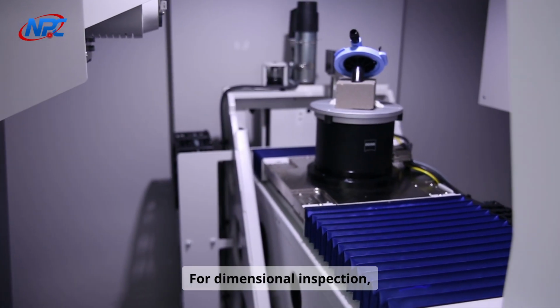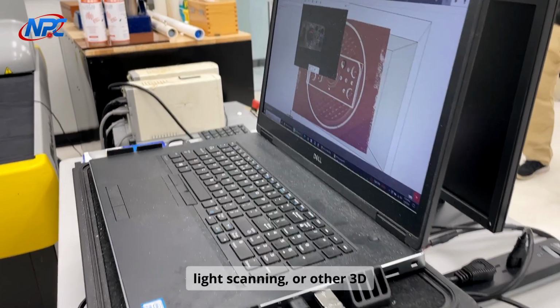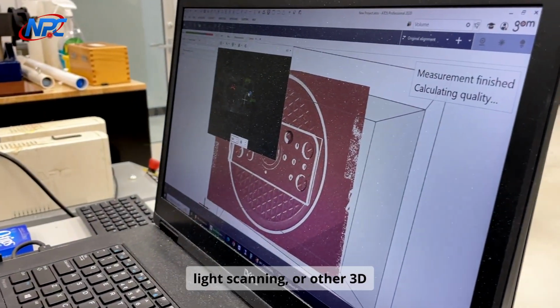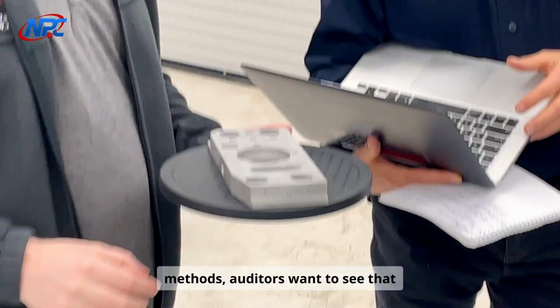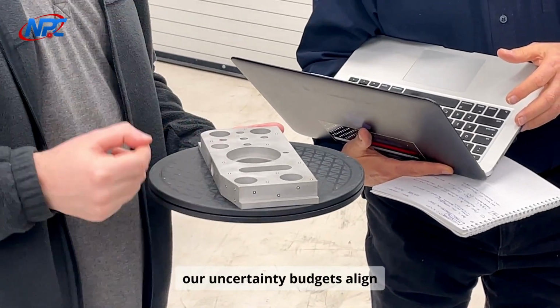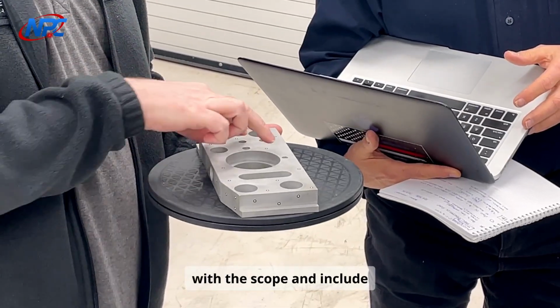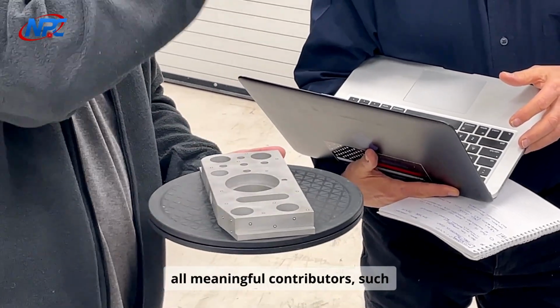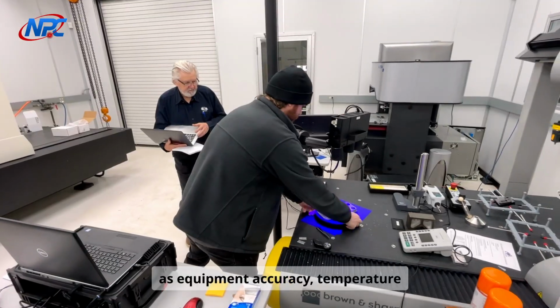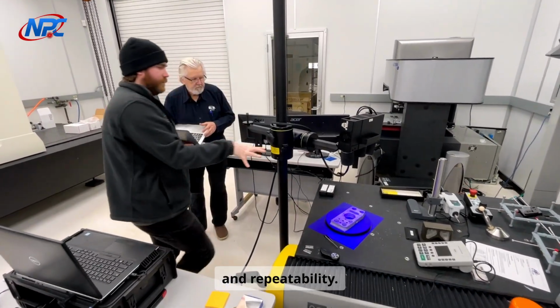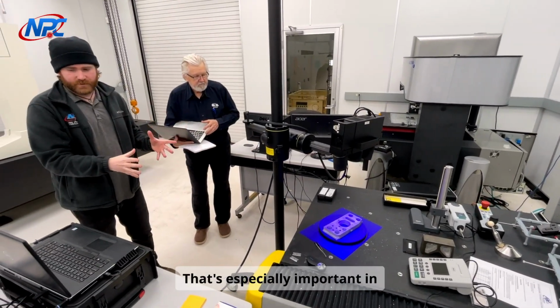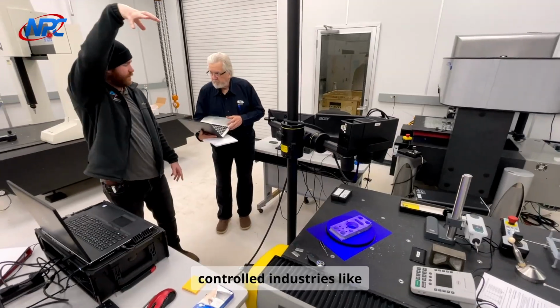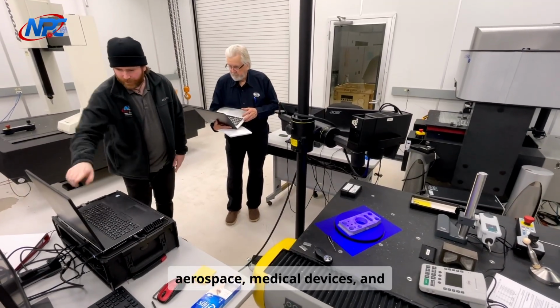For dimensional inspection, whether it is CT scanning, blue light scanning, or other 3D inspection methods, auditors want to see that our uncertainty budgets align with the scope and include all meaningful contributors, such as equipment accuracy, temperature effects, resolution, and repeatability. That's especially important in controlled industries like aerospace, medical devices, and defense.